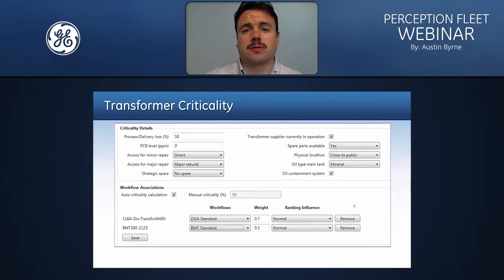One of the critical factors whenever evaluating a transformer is understanding the transformer's criticality. Within Perception Fleet, we're able to capture the transformer criticality information, as you can see on your screen now. We look at certain areas such as the power delivery loss percentage, PCB level, access for minor repair, access for major repair, strategic spares, as well as a host of other information that helps us evaluate the criticality of the transformer. All this information is taken into account whenever the risk index is calculated for the transformer.